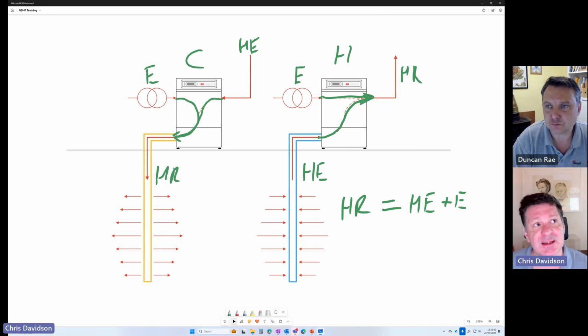So the range of heating efficiencies that you normally expect would be sort of 3 to 4 units of heat being delivered into the building for every unit of electrical energy that's being consumed. You'll actually get slightly higher efficiencies than that in cooling, because the temperatures at which you're cooling are very close to the temperatures that we're encountering in the ground. But typically speaking, 3 to 4 units of heat being delivered for every unit of electrical energy. Now, if we've got a heating and cooling system, or there's some heat recovery going on in the system, which I'll talk about in a second, then those efficiencies can be significantly higher.